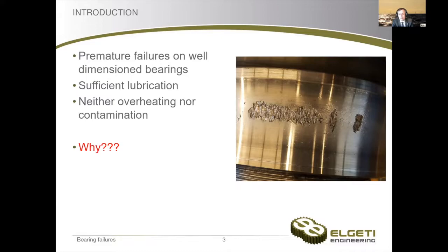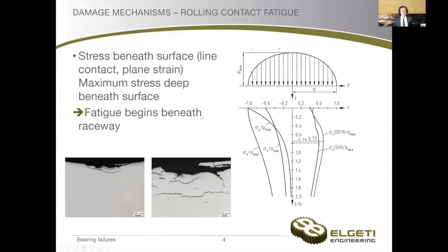So firstly, what is this topic on white etching crack failures about? Well, we face some bearings where we have premature failures and everything seems to be fine. The bearings are well dimensioned, we have sufficient lubrication, we have neither overheating nor contamination nor whatsoever that could possibly explain some premature failures, but still somehow suddenly we see raceway flaking, like in this case on the inner ring of a spherical roller bearing. And now the question is why — how is this possible?